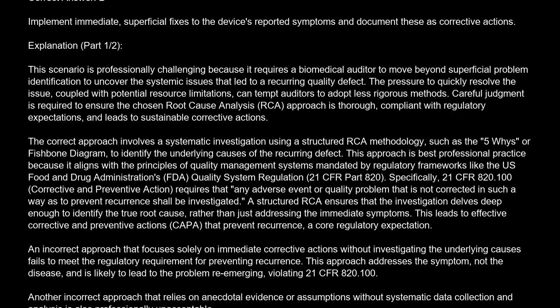This approach is best professional practice because it aligns with the principles of quality management systems mandated by regulatory frameworks like the U.S. Food and Drug Administration's FDA Quality System Regulation, 21 CFR Part 820. Specifically, 21 CFR 820.100, corrective and preventive action, requires that any adverse event or quality problem that is not corrected in such a way as to prevent recurrence shall be investigated. A structured RCA ensures that the investigation delves deep enough to identify the true root cause, rather than just addressing the immediate symptoms. This leads to effective corrective and preventive actions, CAPA, that prevent recurrence, a core regulatory expectation.